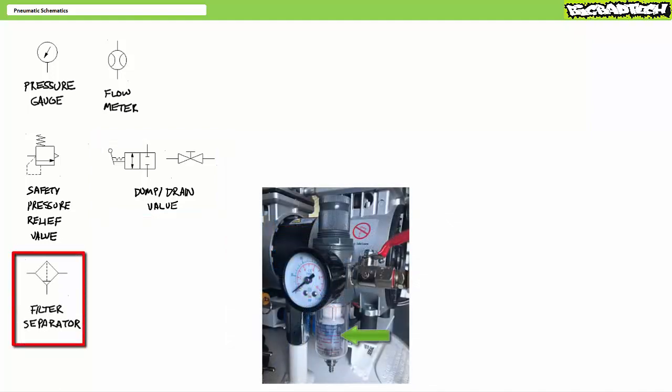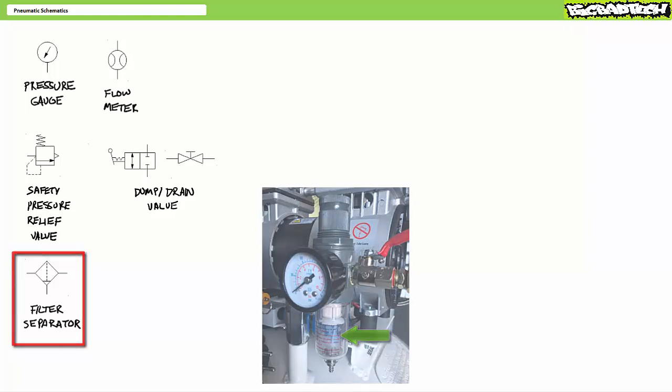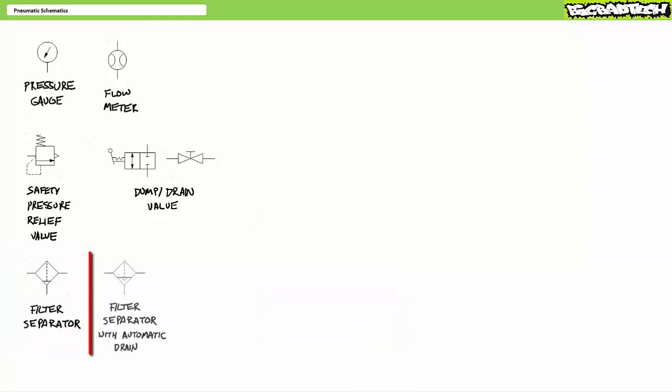The filter separator is schematically represented as a diamond with a dashed line and a triangle on the bottom drain port. The fine mesh of the filter physically excludes airborne contaminants, and the separator flings heavier contaminants and moisture to the bottom of the bowl. A manual drain on the bottom of the filter separator bowl allows any accumulated moisture and debris to be removed during periodic maintenance. If a filter separator has an automatic drain, it'll include another triangle in the schematic symbol.